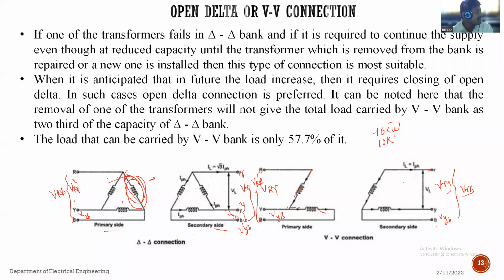Delta bank ची 2/3 capacity तो carry करू शकत नाही. In an open delta system it will carry near about 57% or 2/3 of the capacity of the delta bank, so near about it will carry 60 to 70%. The load that can be carried by the VV bank is only 57.7% of it. म्हणजे VV bank it will carry a load near about 57.7%. Here there is less load on the transformer, that is near about 60% load will be present on that capacity transformer. At that situation we are able to do that type of connection.